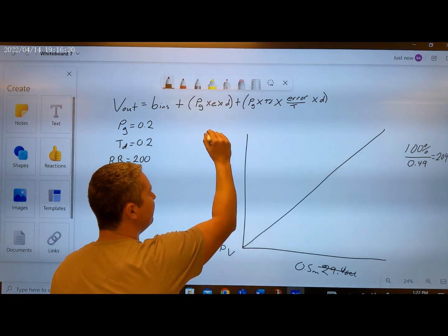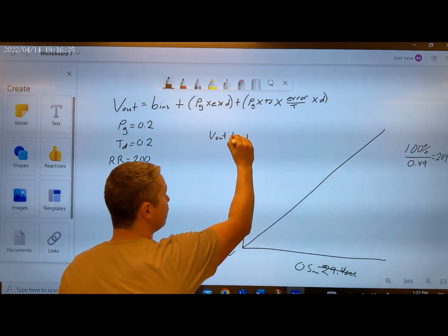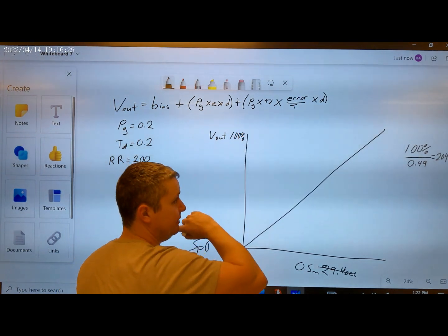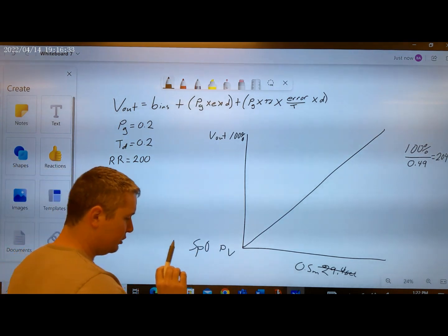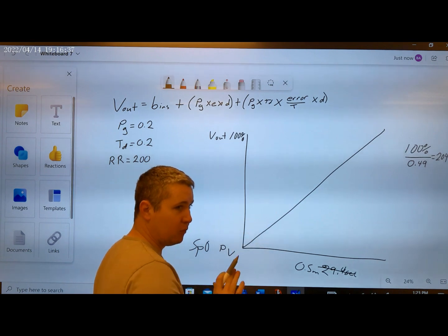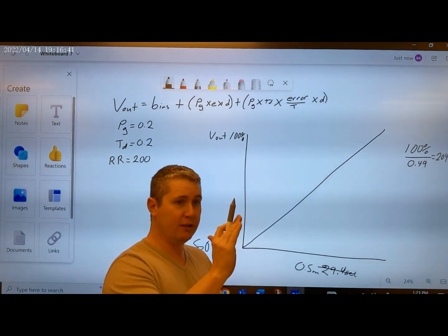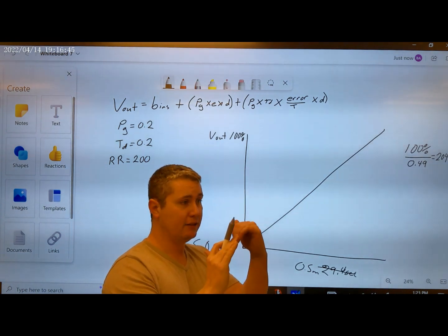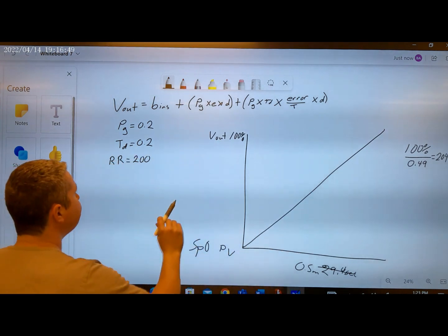Our output, our valve out, is currently at 100%, okay? That's our bias, is 100%. What derivative does is it acts against a ramp rate. Whenever it sees a ramp rate, it wants to, in reverse acting, counteract that ramp rate, okay? We're going to see that here.